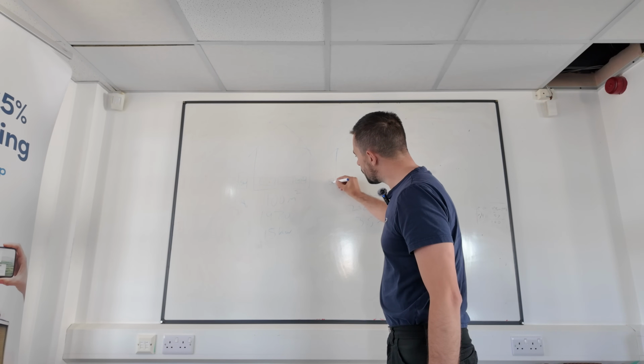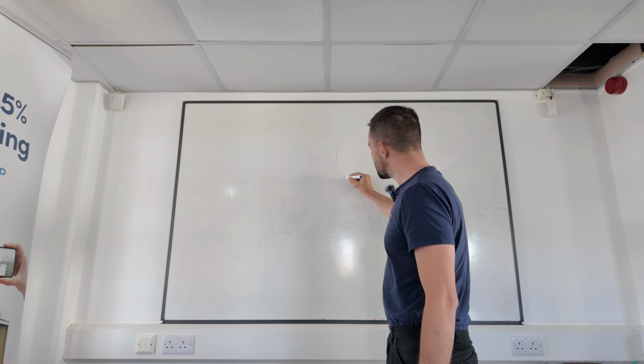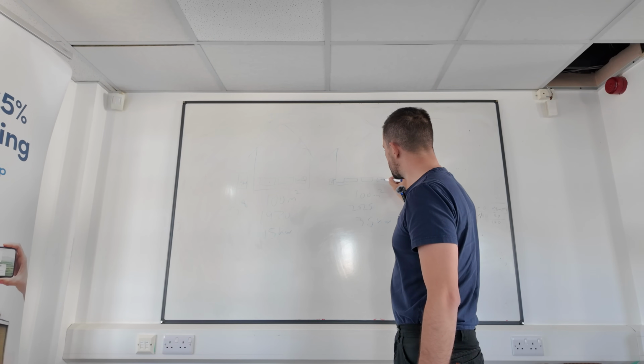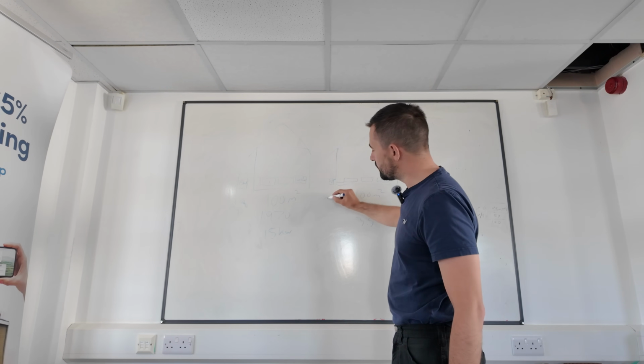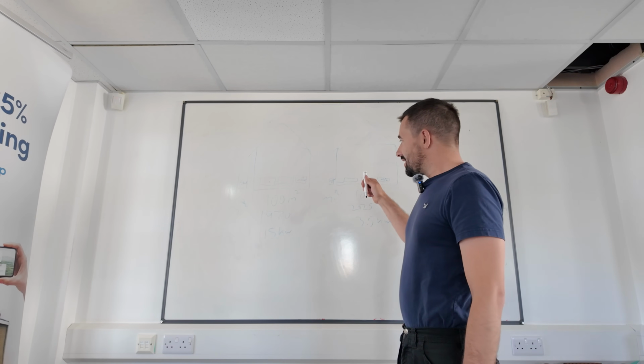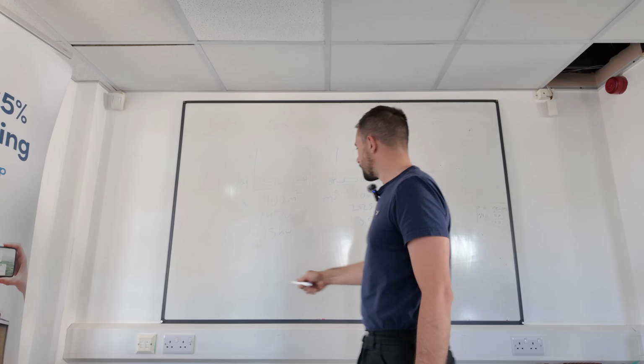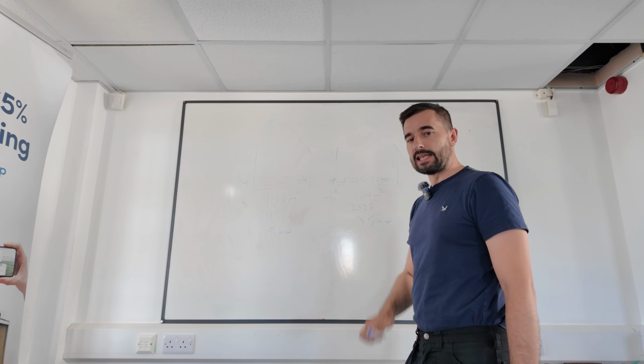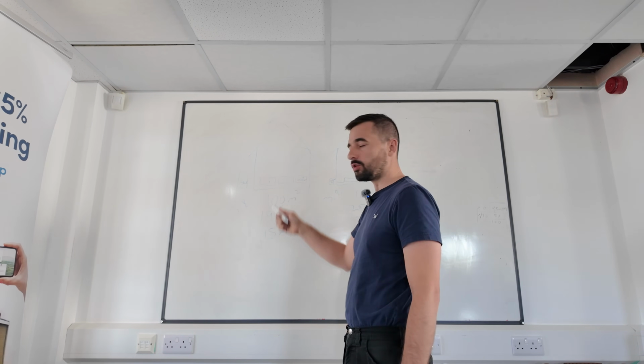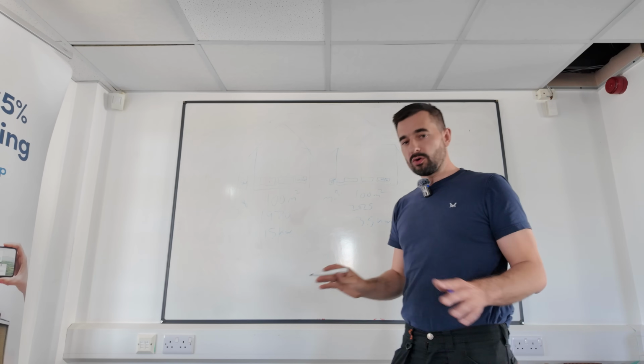This new house, if I was to install a 3.5 kilowatt heat pump on it, with radiators, obviously a lot smaller than those, designed at 45 degrees Celsius, I will get an efficiency of 3.8-ish, okay? That'll be warm, that'll have a seasonal efficiency of 3.8, as will that. Now, the only difference is the capital expenditure to do that one will be higher than that one. But both will be warm, both will be efficient, both will work.